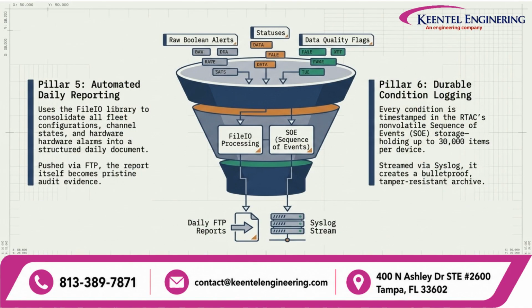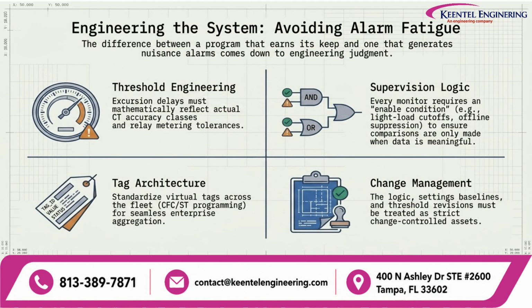Finally, we automate reporting and logging. Using the File I/O library, all conditions are consolidated into structured daily reports, while the sequence of event storage provides a tamper-resistant audit trail. To avoid alarm fatigue, we emphasize threshold engineering and smart supervision logic. Properly managing virtual tags and implementing strict change control ensures your system remains reliable and effective.